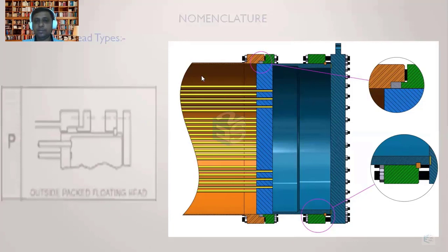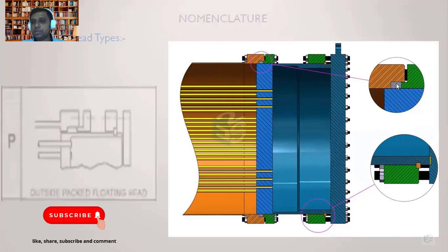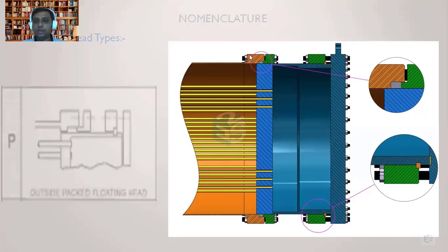For the shell side: shell side fluid comes in, and since the tube sheet, shell, and entire assembly move due to thermal and pressure expansion, there are chances of leakage at this location. To avoid that, the gland packing is placed on the top surface of the tube sheet, inside the groove of the flange that is welded to the shell side.